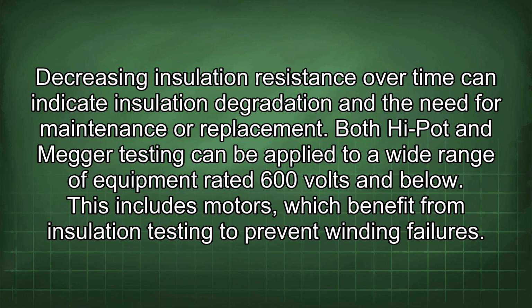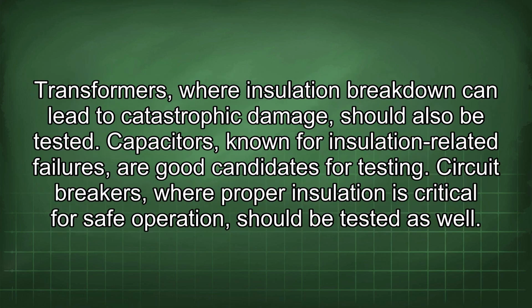Both high pot and Megger testing can be applied to a wide range of equipment rated 600 volts and below. This includes motors, which benefit from insulation testing to prevent winding failures. Transformers, where insulation breakdown can lead to catastrophic damage, should also be tested. Capacitors, known for insulation-related failures, are good candidates for testing. Circuit breakers, where proper insulation is critical for safe operation, should be tested as well.